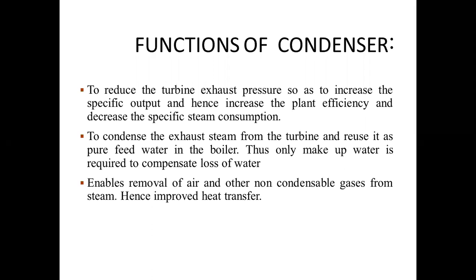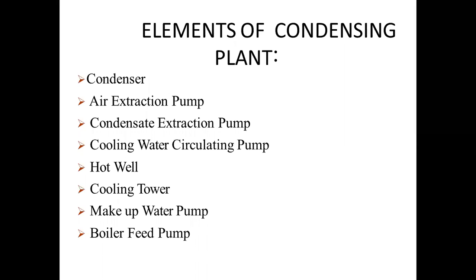Now, what is the function of a condenser? The function of the condenser is to reduce the turbine exhaust pressure so as to increase the specific output and hence increase the plant efficiency and decrease the specific steam consumption. It condenses the steam from the turbine and reuses it as pure feed water in the boiler. Thus, it makes less use of fresh water; only the water which gets lost due to evaporation is required to be compensated. It enables removal of air and other non-condensable gases from the steam, so it improves heat transfer. There are various elements of a condensing plant: the condenser itself, air extraction pump, condensate extraction pump, cooling water circulating pump, hot well, cooling tower, makeup water pump, and boiler feed water pump.